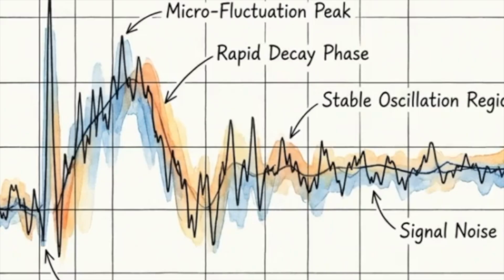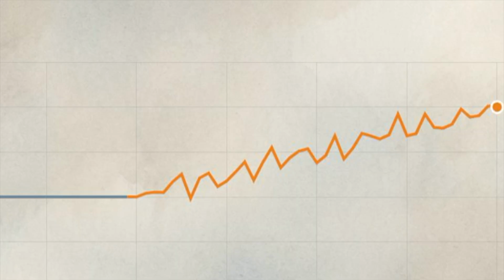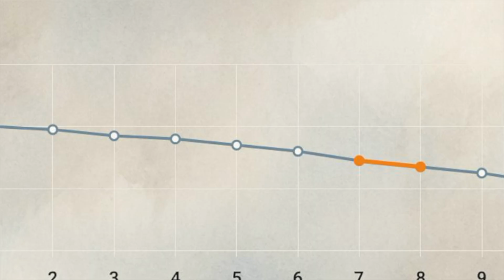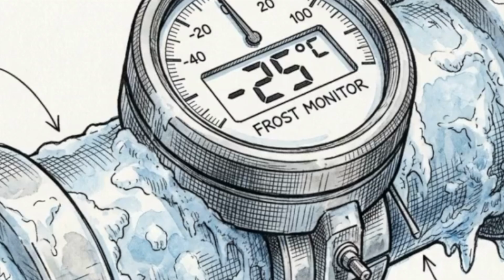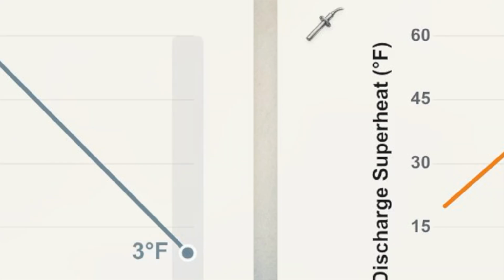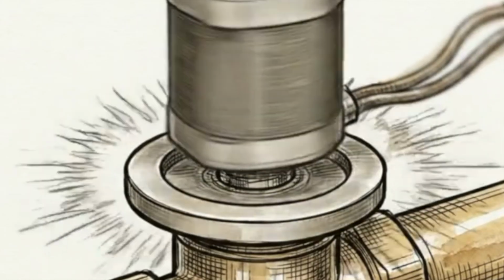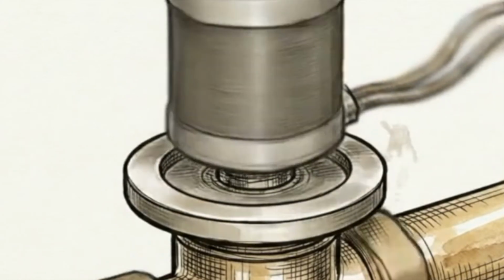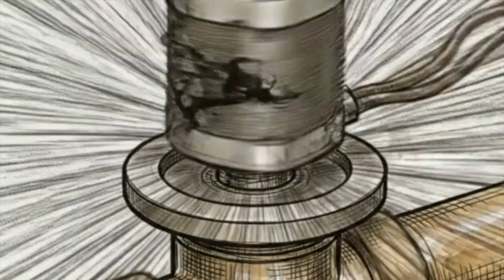The actual target of predictive maintenance is mapping transient dynamic data. We have to look at how the system behaves while shifting between states, rather than measuring fixed, steady-state outputs. The earliest indication of a developing fault is a highly specific, microscopic drop. The system will show a subcooling decline of exactly 0.2 of a degree Fahrenheit per week. This drop is followed by a secondary confirmation signal, a steady, unnatural climb in the compressor's discharge superheat over that exact same time frame. These subtle thermal shifts culminate in a final warning. The expansion valve's stepper motor aggressively microfluctuates, losing stability under immense pressure.